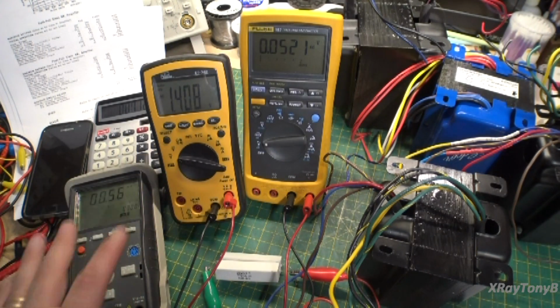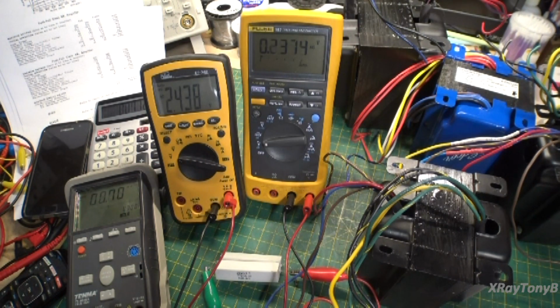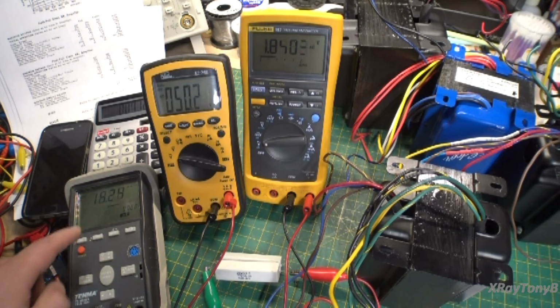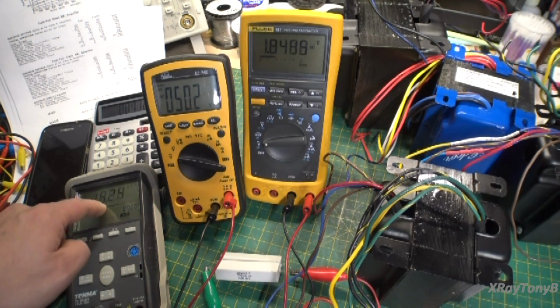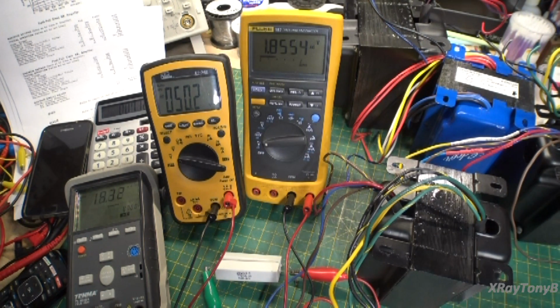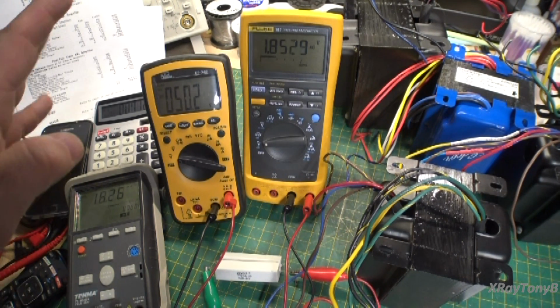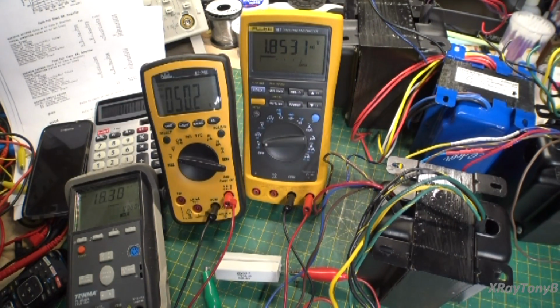You're going to find out the input's going to change a little. The voltage will be the same, but these guys are all going to be a little bit different. So look what's happening now. As I go up to my 50 volts, you see there? There's 50 volts, and at 50 volts now, I'm getting almost the same current through there that I was at 100 volts when I was connected to the 4 ohm tap. And my output voltage, instead of 2.7 volts now at 100, I'm getting about 1.8 volts at 50 volts. So as you can see, it makes a huge difference.